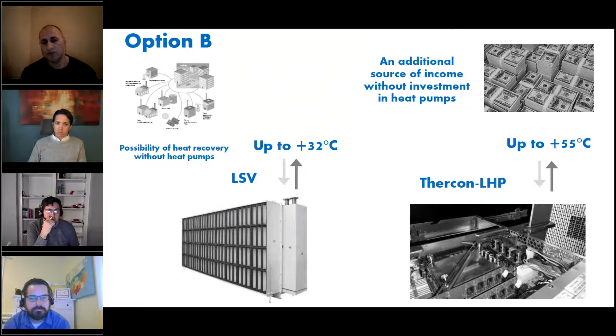So a few words about LHP. LHP is a passive loop heat pipe which is heated up by the processor and itself transfers the energy to the end of the rack, where the passive heat sink is installed, and through it the liquid goes with high temperatures. By the way, when we decrease the quantity of fans in servers, IT load is reduced by 5–10%.